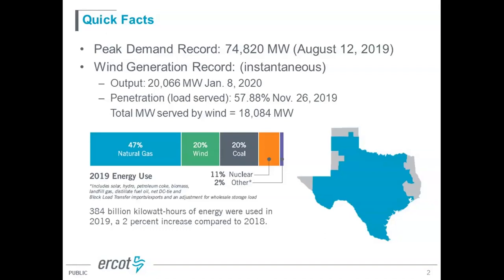The historical peak demand was close to 75 gigawatts, recorded last year. In terms of interconnection, we do have a DC type connection to our neighbors, but it's a relatively small amount, less than 1.2 gigawatts compared to the close to 75 gigawatts of load that we have. So from the operation perspective, we really manage the voltage and the frequency relying on all the resources within ERCOT. There is very limited support, and also kind of no support from the DC ties for the voltage and the frequency support.